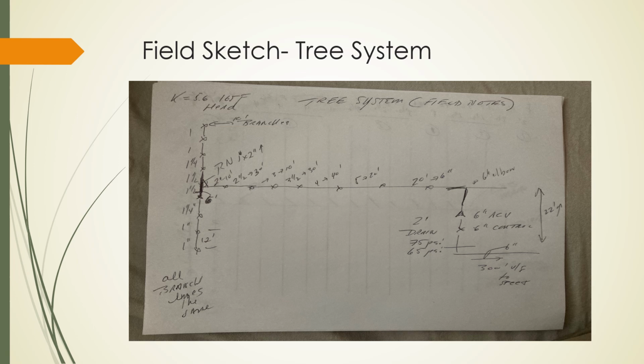Now, I've calculated hundreds of sprinkler systems. We used to have a coded system called Walsh back in the 80s. Then we went to a graphical system in about 2000, and in 15 to 20 minutes, I can punch this into a system and grab some numbers. But even without that, one other piece of information, I've also gone into the cabinet, and I've pulled a head that's a K 5.6 head at 165 degrees. And so in this particular case, I've also grabbed the 2-inch drain test, and it's 75/65.